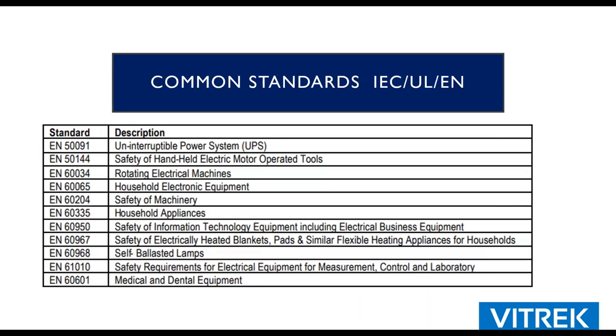All right, so here are some common standards. 61010 is a very common one. That's the one that applies to us. You have different standards for luminaires, UPS systems, household appliances. All of these have a different standard. The tests are similar, yet different, depending on what products you're looking at. Some of you might find some of these numbers familiar. Typically, they're harmonized standards, so that EN could be an ISO, it could be a UL, it could be an IEC standard, and you're going to find the verbiage to be very similar throughout all those different standards.